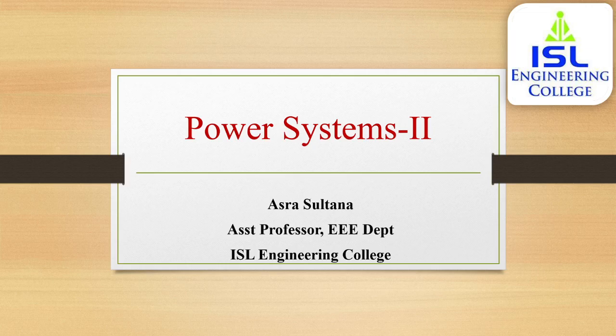Let it be I. Then various short circuit calculations will be: ISC, that is short circuit current, is equal to I into 100 by percentage X. Short circuit kVA is equal to base kVA into 100 by percentage X. Then we have done a few numericals based on this topic.